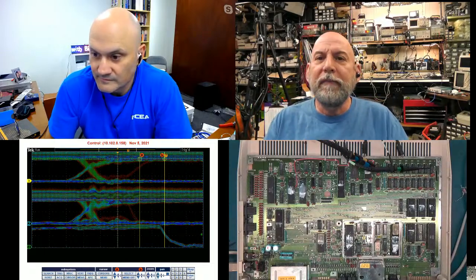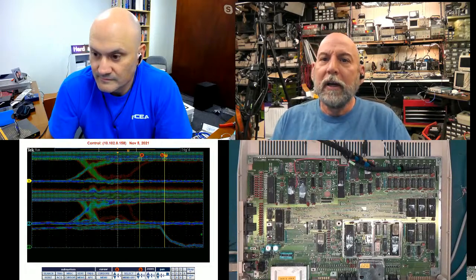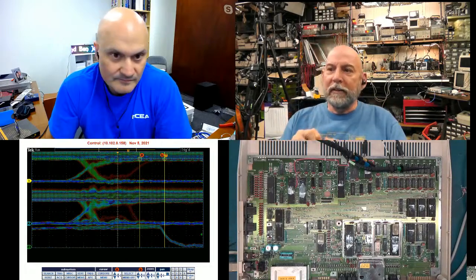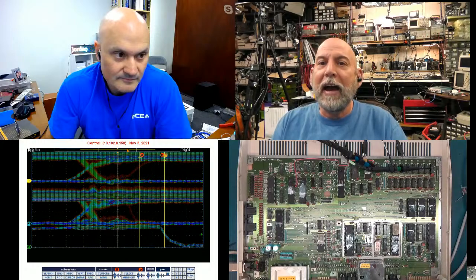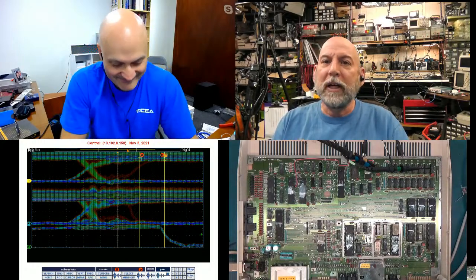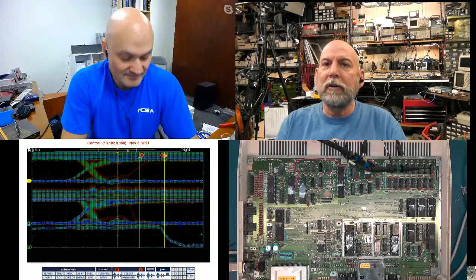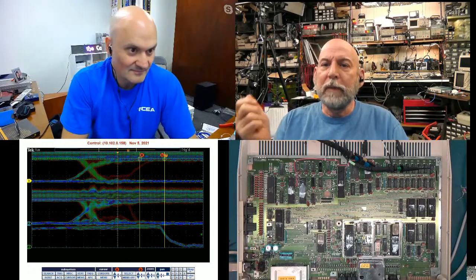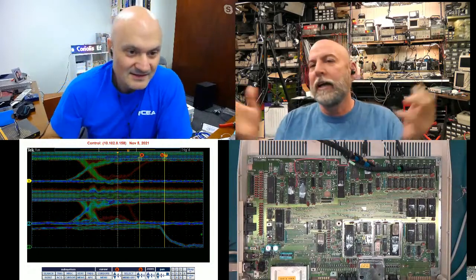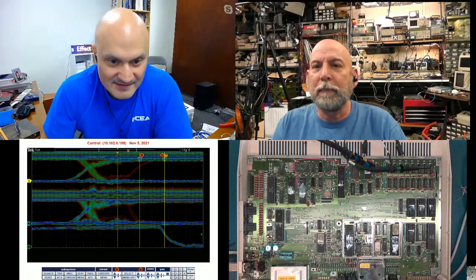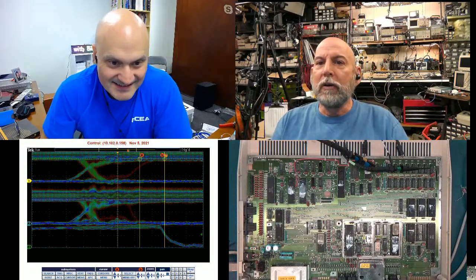That's fine if it already wants to be earth ground. But if it wants to be a floating ground - and I'm sad to say I've had it happen once, it happened when I slipped - I didn't intentionally go to ground on a floating ground, but I slipped with my ground probe and popped the fuse. I had to fix it and got it right back up and running. So you need to be cognizant of that.